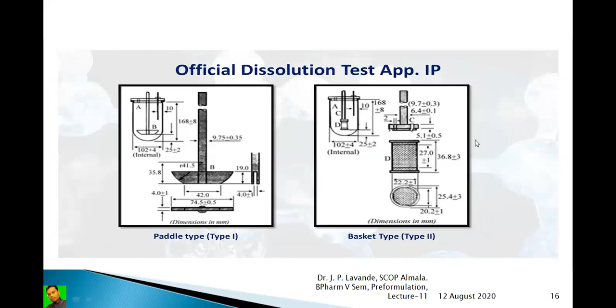Now here you can see the official dissolution test apparatus of the USP. In the USP, the rotating basket is apparatus number 1, whereas apparatus number 2 is the rotating paddle. Whereas in the IP, we find the rotating paddle as type 1, and the rotating basket as type 2. As per the IP, the rotating basket is type 2 and the paddle type is type 1. But as far as the USP is concerned, the rotating basket is apparatus number 1, and the rotating paddle is apparatus number 2.